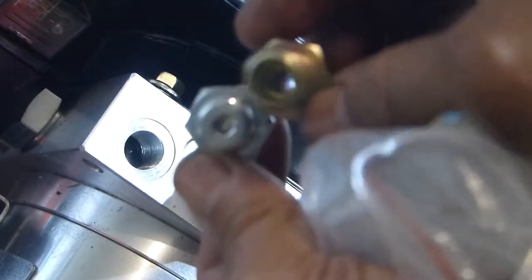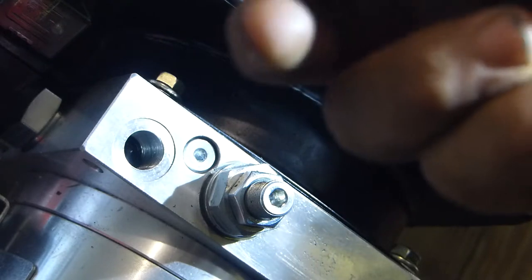Yeah, they're both matching the BSP to BSP British pipe thread. Your volume on this is restricted. It's hugely different than the volume on these guys. One in the right hand over here has much more volume, as you can see the holes. So with that said, we're gonna get quicker response times if we go with this one.